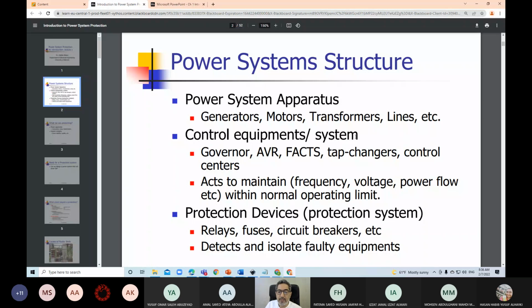So the control system can be done through the generator governor. Do you know about the generator governor, guys? It's like a valve that controls the steam intake to the steam turbine, or the gas to the gas turbines, or the water to the hydro turbines. And the AVR, which is the automatic voltage regulator, is the one that regulates the excitation to the synchronous machine. So this is the controller that maintains the voltage at the terminal of the generators.